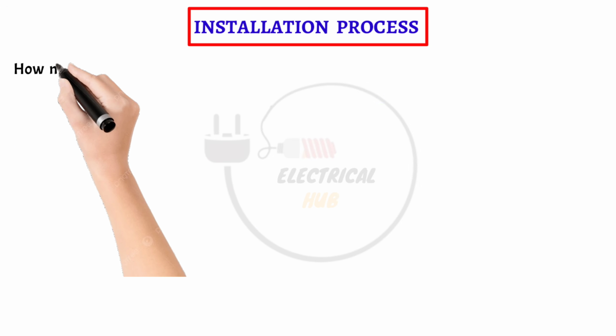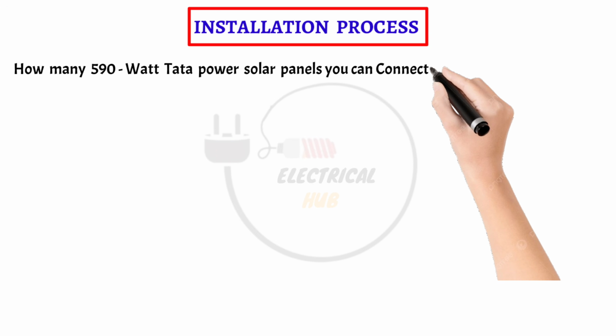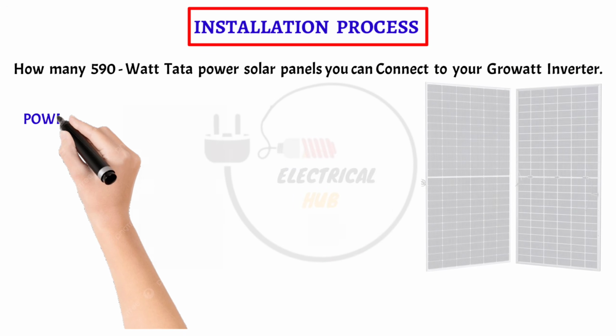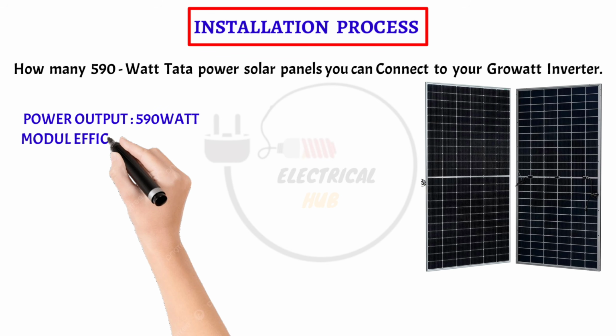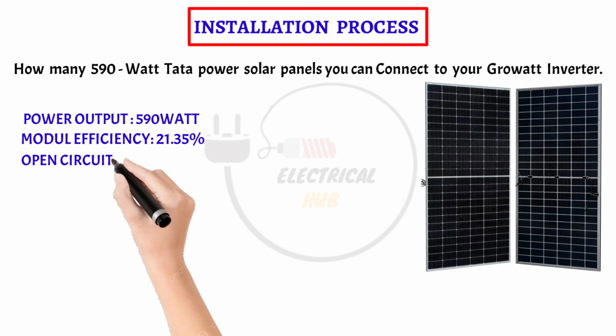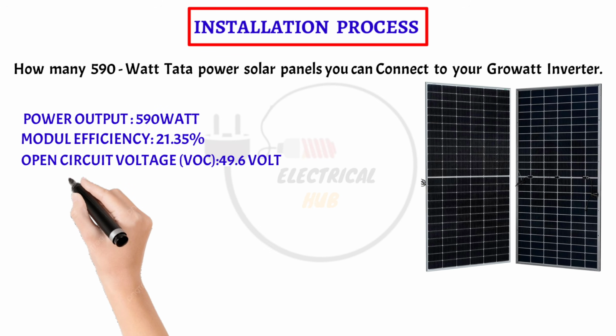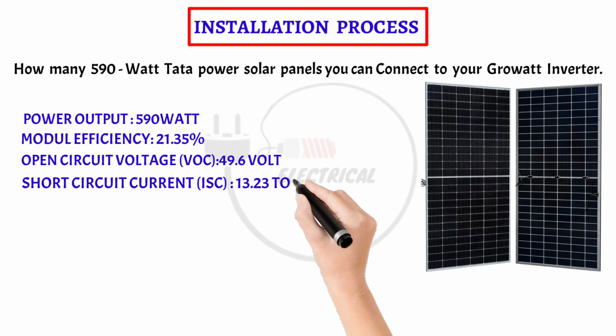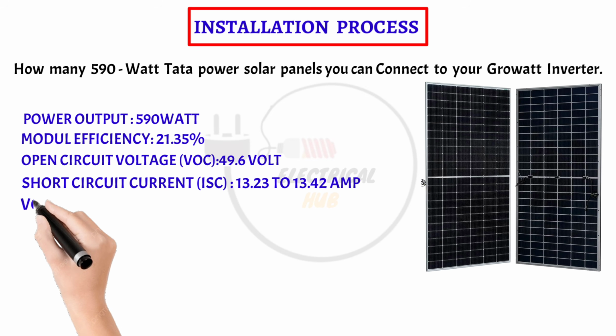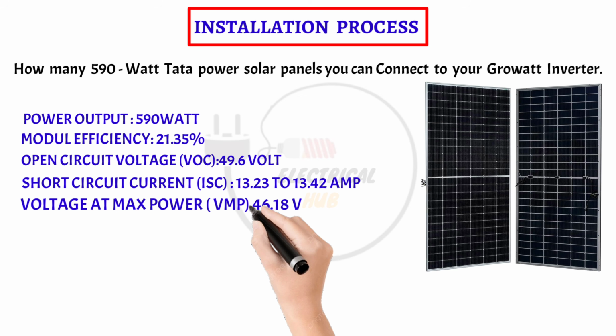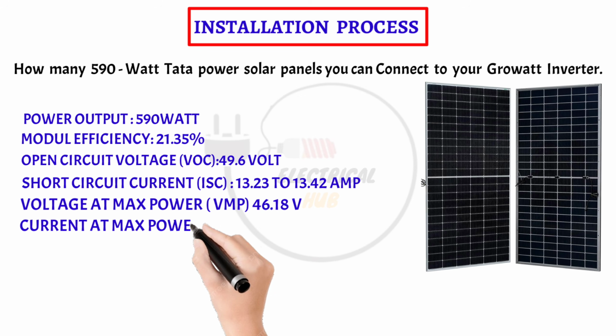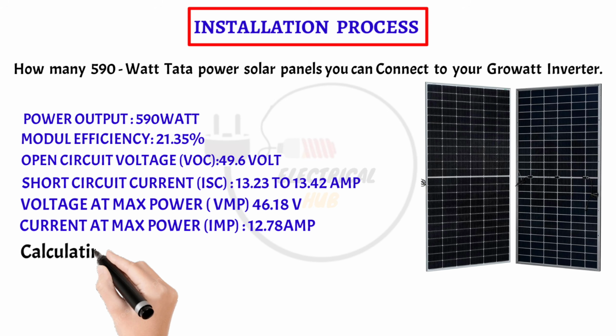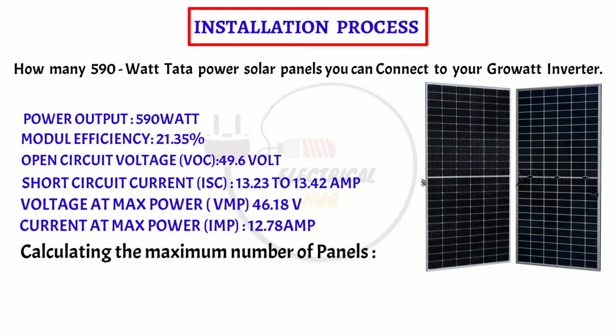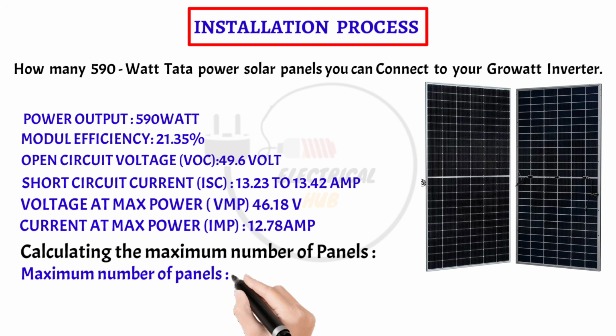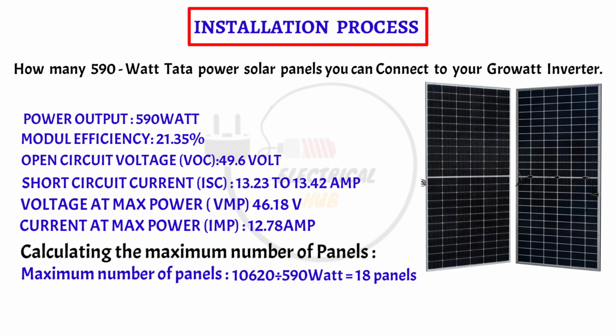Okay, let's figure out how many 590 watt Tata Power Solar panels you can connect to your Growatt inverter. Power output 590 watt. Module efficiency 21.35%. Open circuit voltage VOC 49.6 volt. Short circuit current ISC 13.23 ampere to 13.42 ampere. Voltage at max power VMP 46.18 volt. Current at max power IMP 12.78 ampere. Now calculating the maximum number of panels. Divide the inverter maximum PV input power by panel wattage. Maximum number of panels equals 10,620 watt divided by 590 watt, which equals 18 panels.